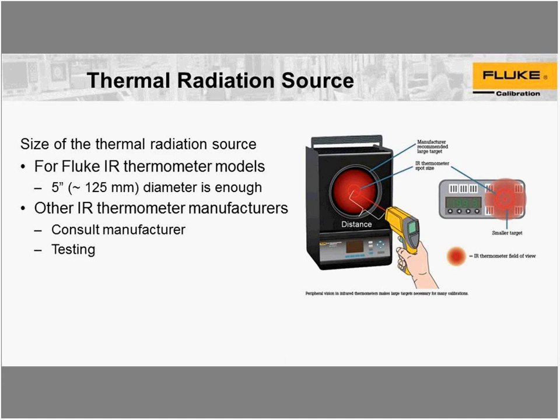For any Fluke IR thermometer model, 5 inches or 125 millimeters diameter is enough for the calibration. We don't just use the spot size — there is stray radiation that comes from outside the field of view of the infrared thermometer. It's well known that when the field of view is specified, 90% of the radiation the IR thermometer reads comes within the circle; the other 10 percent comes from outside, and this is scatter. We know that for Fluke IR thermometer models, 5 inches or 125 millimeters is enough. If you use a smaller target, you risk some radiation coming from outside, which will be either an uncertainty or an error in your calibration.